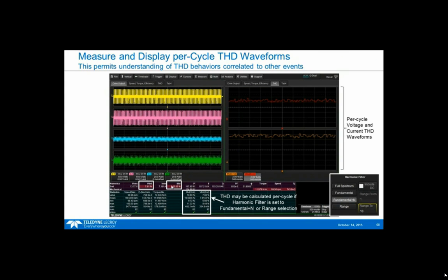I can take that value, click on that table cell, and it'll plot that over time. Here we show an orange waveform, the current total harmonic distortion for the complete drive output, and red is the voltage harmonic distortion for the complete drive output three-phase system, plotted over time. They're fairly constant, which is reassuring. They're a little higher than you'd like, but that's really the design of the motor. As I said, this is more of a research project, not a fully developed motor in a vehicle today, so the harmonic distortion could be one of the trade-offs they're willing to accept. In any case, the THD values are very constant over time.